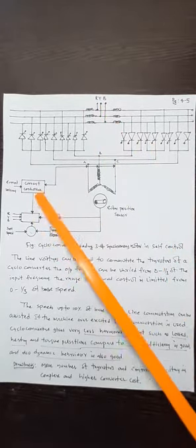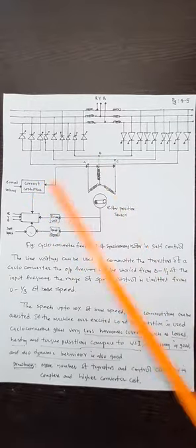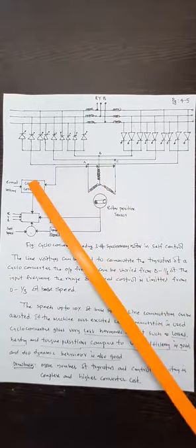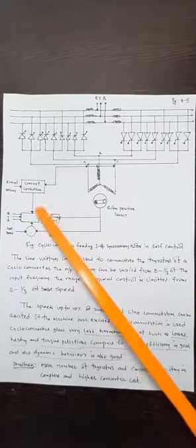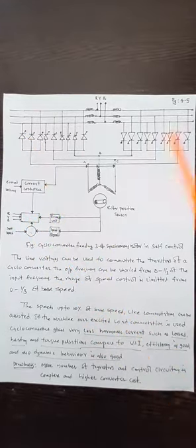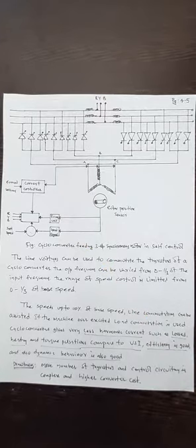Yes. So a current controller is also there. The current is sensed by the current sensors and provides the quality of firing signals to all the 18 thyristors. This is the simplified system where variable voltage is possible and variable frequency is possible, so that the speed of the synchronous motor for below rated speeds as well as above rated speeds is obtained easily.